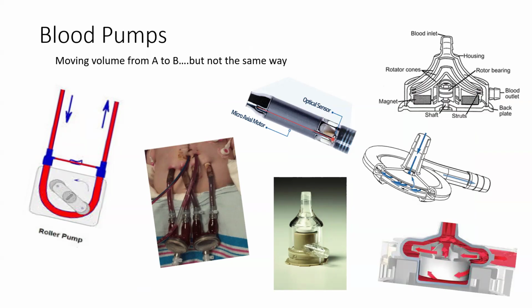You have other types of pumps, like the second picture there. That's a Berlin Heart. That's a pulsatile air pump. Not something that you'll use in ECMO, but a blood pump that's out there that's an extracorporeal life support device. Then you have something like the Impella. Right? The Impella is an axial screw with ceramic bearings on which it spins.